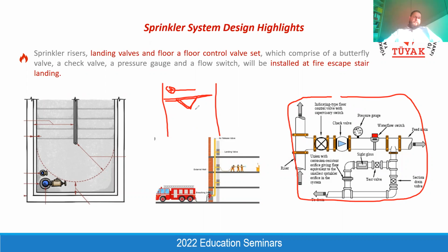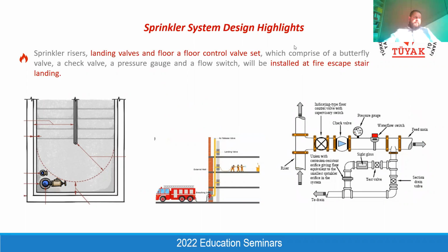It is not allowed because during a fire incident, both the technical team of the building and also the fire brigade should reach the landing valve, should reach the valve group of the sprinkler system easily without being affected by the fire, as we explained for the fire pump group. The landing valve and the floor gate valve group should always be accessible during a fire incident. That's why we need to locate them within the fire escape staircases.